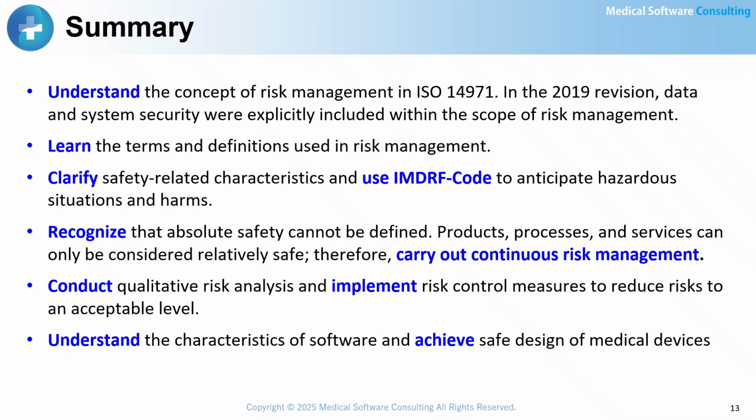Products and services can only be relatively safe, so we must carry out continuous risk management. Conduct qualitative risk analysis and implement risk control measures to reduce risks to an acceptable level. And finally, understand the characteristics of software and design medical devices with safe design principles in mind. By applying these concepts, manufacturers can ensure compliance with ISO 14971 and contribute to the development of safer, more reliable medical devices.